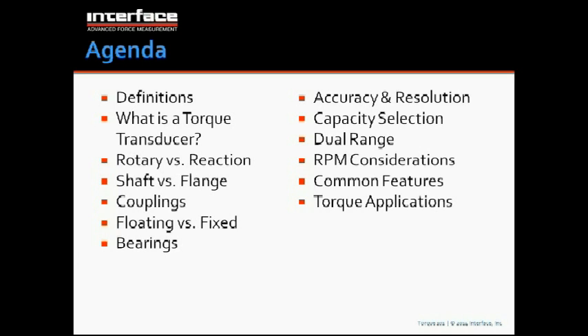We'll talk about some definitions that relate to torque, talk about what is a torque transducer, talk about different types of torque transducers, rotary, reaction, shaft versus flange style, talk about mounting, we use couplings, talk about fixed or floating mount. Sometimes we need to use bearings. Sensors have bearings. Sometimes there also need to be bearings in installation. We'll talk about that a bit.